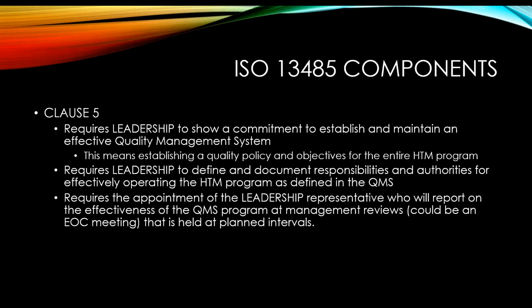So, continuing on, Clause 5 requires leadership to show a commitment to establish and maintain an effective quality management system. This means establishing quality policy and objectives for the entire HTM program. It requires leadership to define and document responsibilities and authorities for effectively operating the HTM program as defined in the quality management system. It requires the appointment of a leadership representative who will report on the effectiveness of the QMS program at annual reviews. Yes, this can be interpreted as the EOC, because they want to make sure it's held on a regular basis.